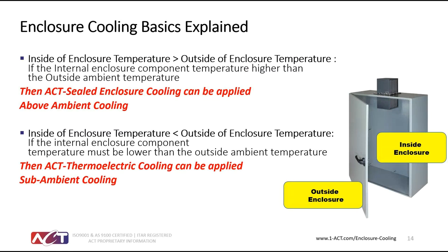And then just to give you a broad explanation of what we're talking about: if the inside of your enclosure is hotter than the outside of your enclosure, then we would call that an above ambient cooling solution. So that would be our heat exchanger products. If the inside of your enclosure is cooler than the outside, or I should say that the outside is hotter than the inside of your cabinet, then you would need to actually air condition it like you probably have typically done, or a thermoelectric cooler can be applied.